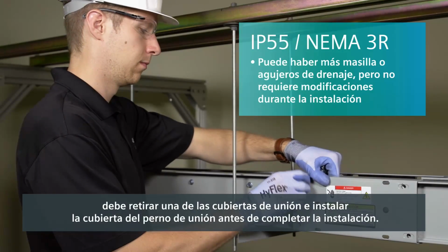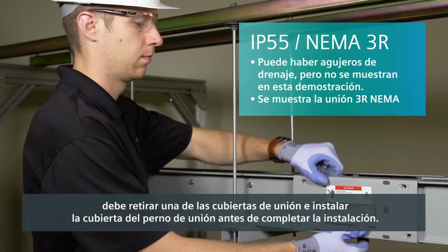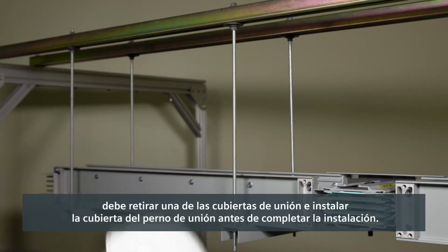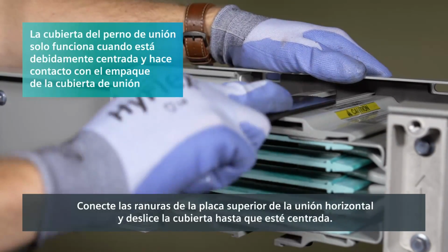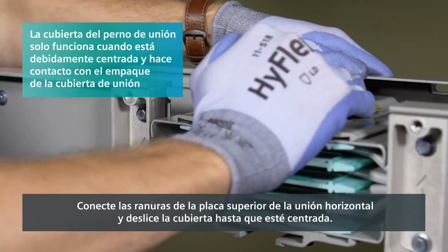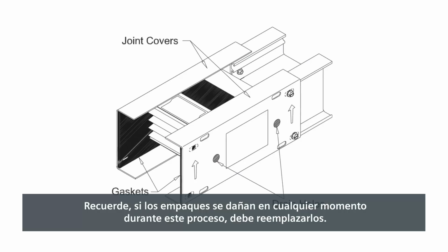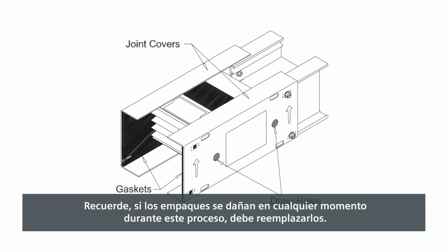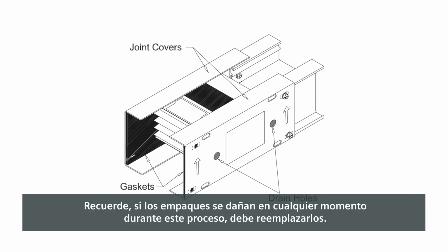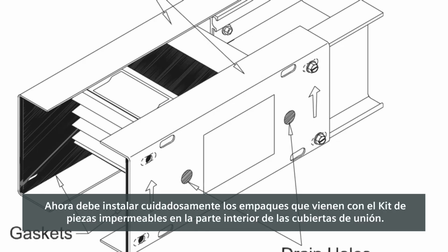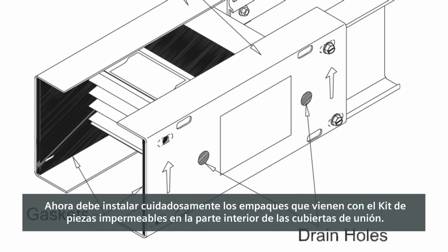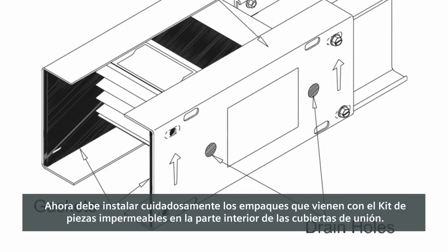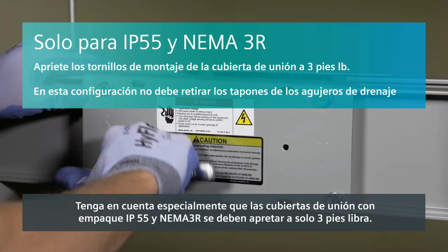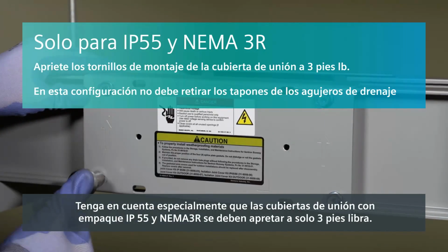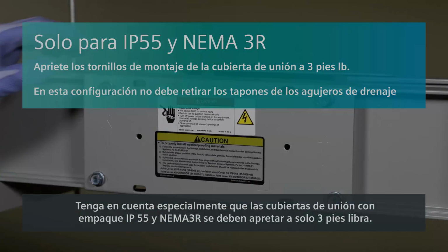For IP55 or NEMA 3R busway, you must remove one of the joint covers and install the joint bolt cover before installation is complete. Connect the grooves on the top plate of the joint stack and slide the cover across until it's centered. Remember, if gaskets are damaged at any time throughout this process, they must be replaced. You should now carefully install the gaskets that come with the waterproof parts kit onto the inside of the joint covers. Take special note that IP55 and NEMA 3R gasketed joint covers should be tightened to only 3 foot-pounds.